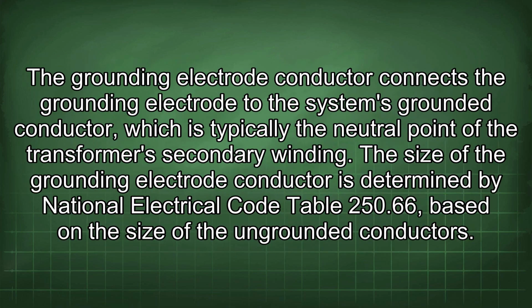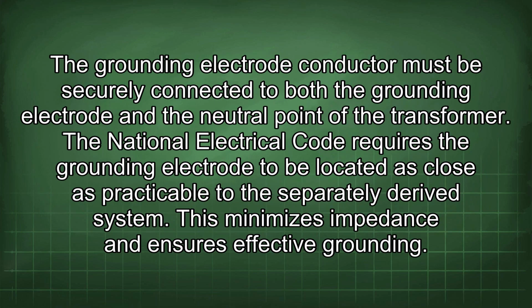The grounding electrode conductor connects the grounding electrode to the system's grounded conductor, which is typically the neutral point of the transformer's secondary winding. The size of the grounding electrode conductor is determined by National Electrical Code Table 250.66 based on the size of the ungrounded conductors. The grounding electrode conductor must be securely connected to both the grounding electrode and the neutral point of the transformer.